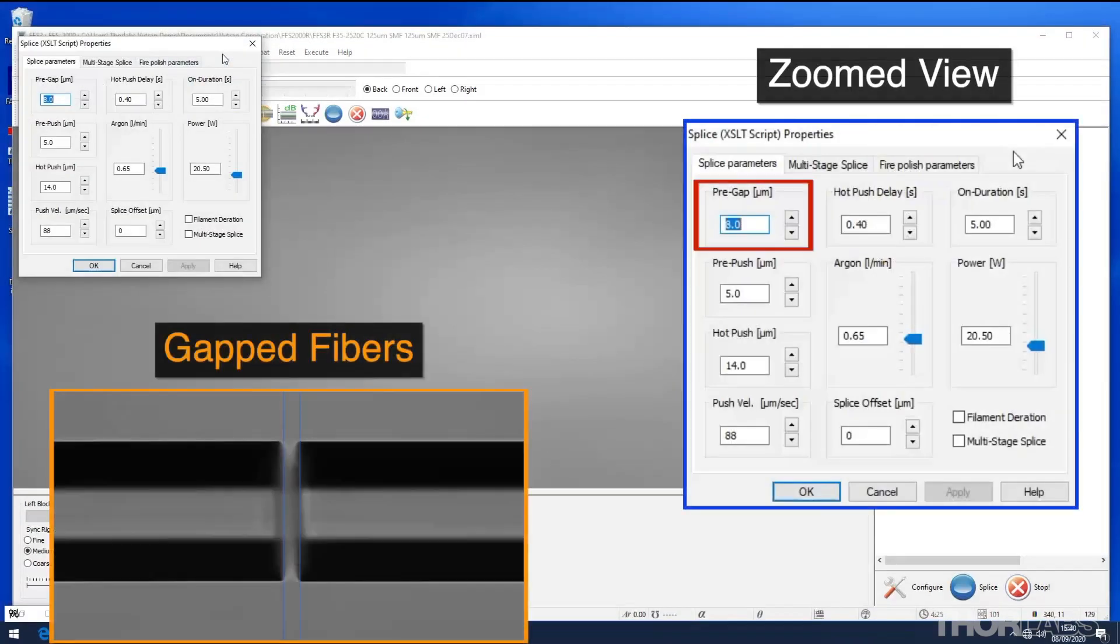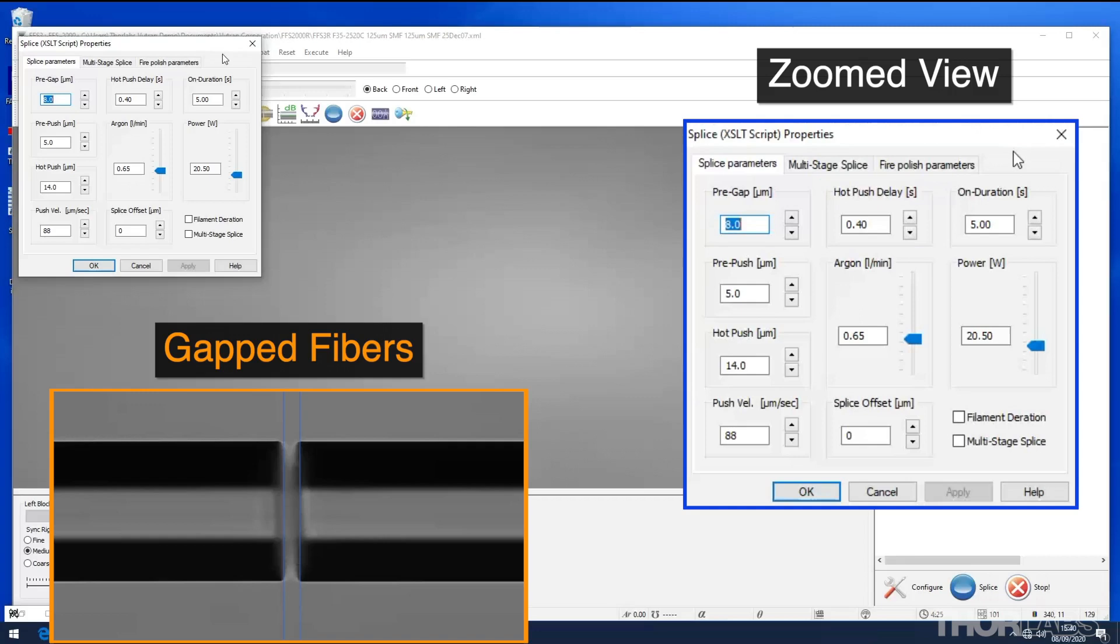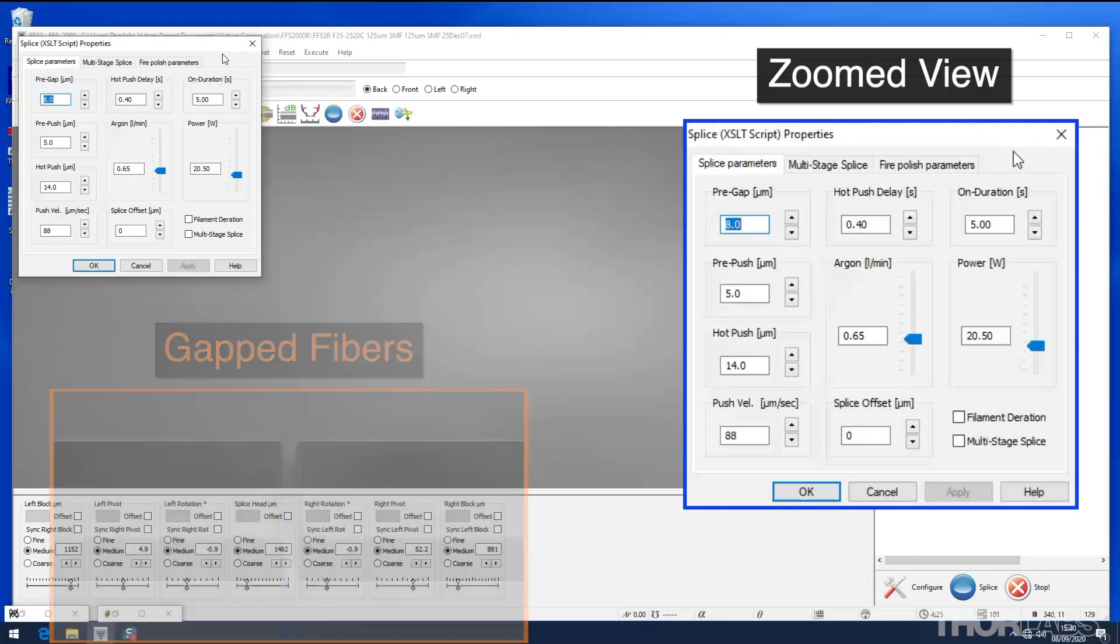Pre-gap, pre-push, hot push, push velocity, and hot push delay determine the timing and movements of the fibers and filament during the splice.